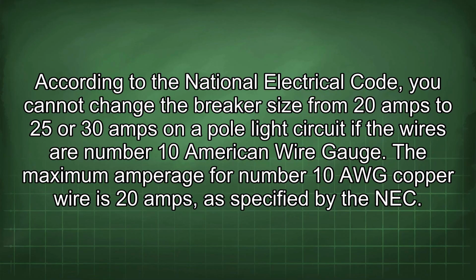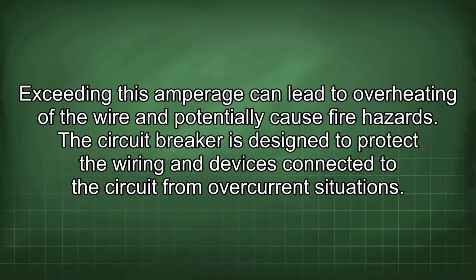According to the National Electrical Code, you cannot change the breaker size from 20 amps to 25 or 30 amps on a pole light circuit if the wires are number 10 American wire gauge. The maximum amperage for number 10 AWG copper wire is 20 amps, as specified by the NEC. Exceeding this amperage can lead to overheating of the wire and potentially cause fire hazards.